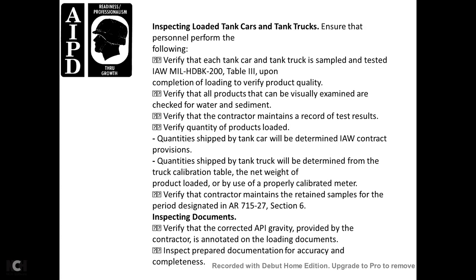After-loading inspection for tanker cars and trucks: verify each tanker car and truck is sampled and tested per Military Handbook 200, Table 3. Verify all products are visually examined for water and sediment. Verify contractor records of test results. Verify the quality and quantity of product loaded; quantity shall be determined per contract provisions using tank calibration tables or net weight measured by a calibrated meter. Verify the contractor retains samples for the required period.